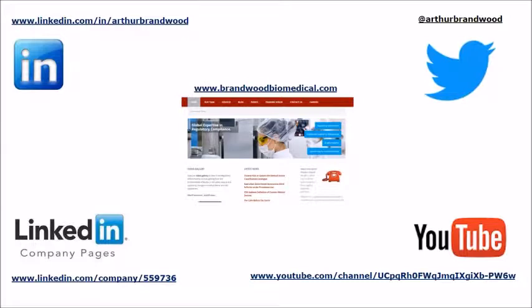I think just the final question, Rach, and for those that we've missed, we'll definitely come back to. Is it possible to extend the response timelines for TFDA review questions during an application? Yes, it is possible. Typically, Taiwan FDA allows the manufacturer or sponsor 60 days to prepare and submit the response, as mentioned in my webinar. But if the manufacturer needs more time, it's typically for the Taiwan local sponsor to send the extension request to Taiwan FDA. And Taiwan FDA normally allows an extension of 1 month, and the extension can only be requested once per submission.